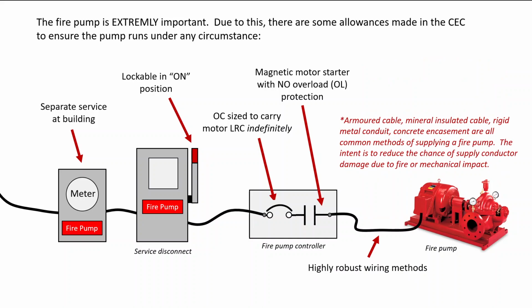Finally, highly robust wiring method from the load side of the fire pump controller to the fire pump itself. Armored cable, mineral insulated cable, rigid metal conduit, and concrete encasement are all common methods of supplying a fire pump. The intent is to reduce the chance of supply conductor damage due to fire or mechanical impact.